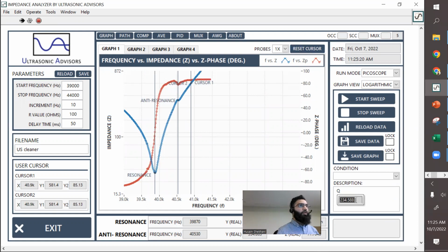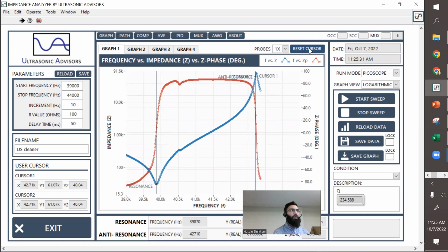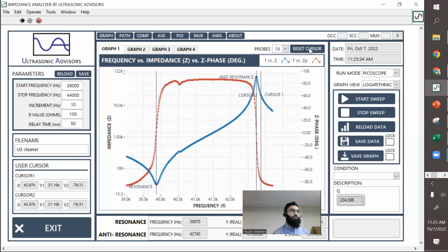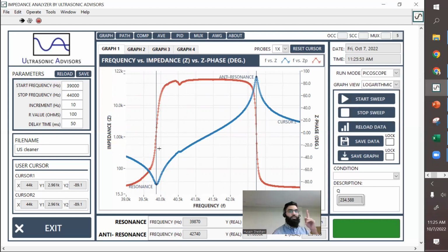Because there's an automatic Q calculator. And again, this is another important point: you should know what your property should be before you start measuring. That is, as I showed by demonstration, an important factor. So how do you measure the quality factor? There are two ways I want to explain: one that's common, and a second that's very important but not as common, though based on the same principles.